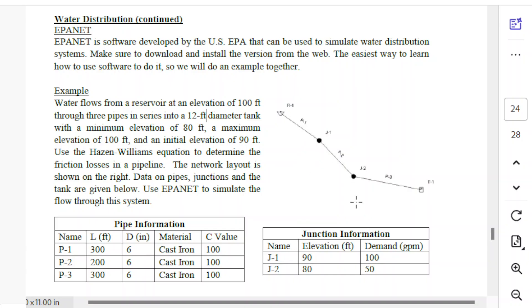We've got two junctions with specified elevations and demands: 100 gallons per minute pulled out at the first junction and 50 at the second. This tells us we need to use gallons per minute for flow in our model. We need to set it up with the Hazen-Williams equation and include all the elevations. Water flows from a reservoir at elevation 100, through junctions at 90 and 80, to a tank where the water level can go up and down.